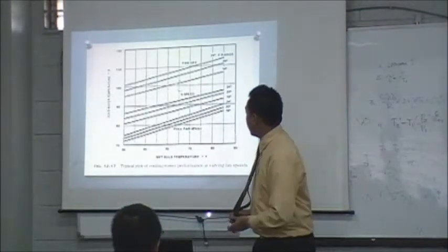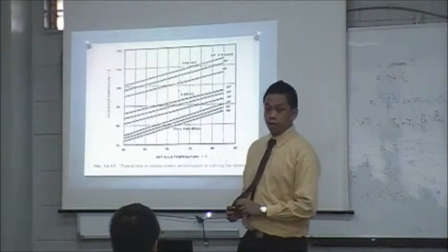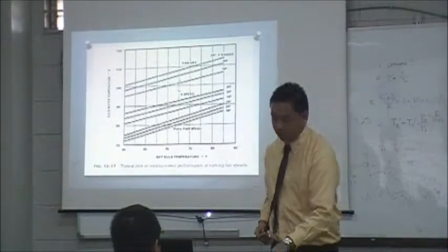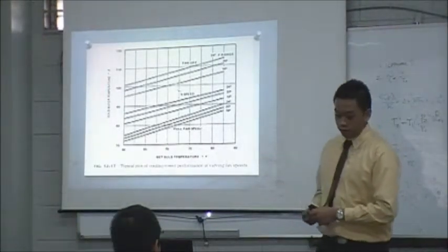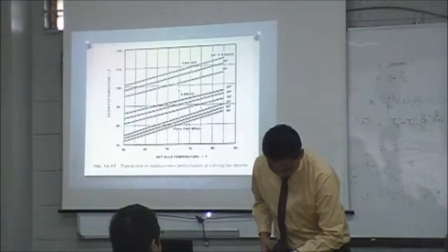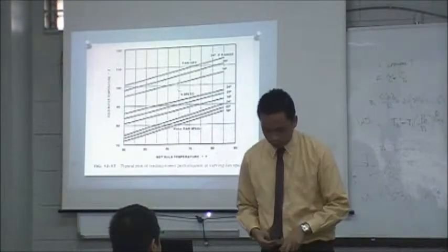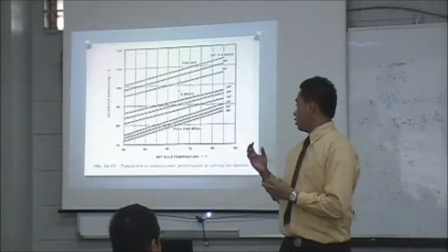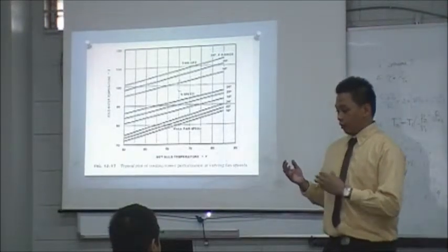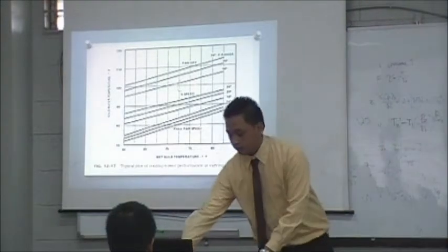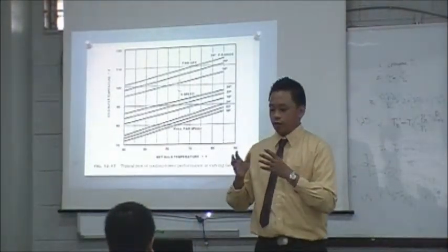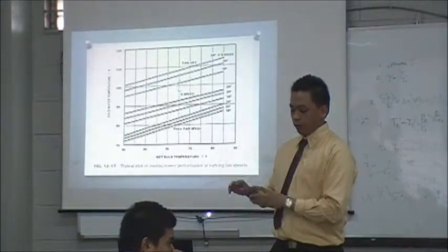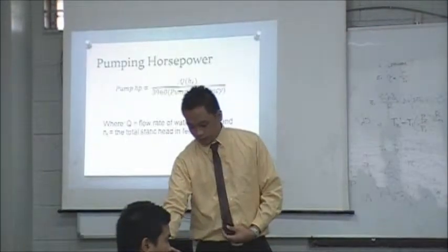If we have a 100 horsepower motor, we'll only consume 17 horsepower to operate the fan. So 83 horsepower would be saved when operating it at half speed. There is a very large power saving when we operate the fans at half speed. It's a matter of weighing which is more costly, using two fans or operating a fan at full speed.